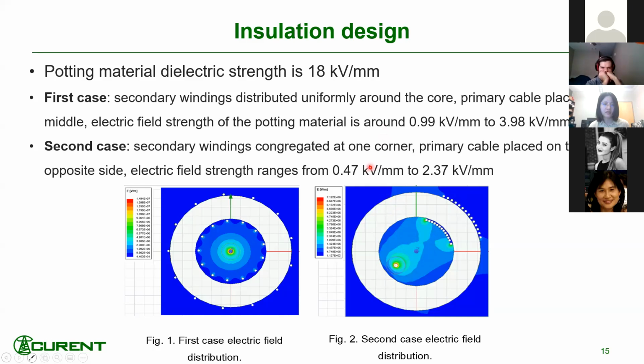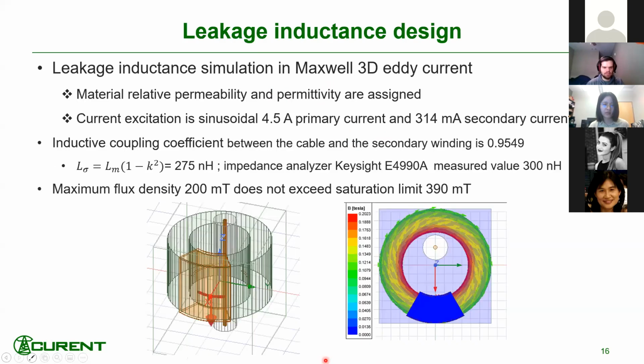So in both cases, the electric field strength is much below this breakdown voltage, which means this transformer would be able to sustain that high voltage. And another issue is the leakage inductance, because the cables and the windings are separated. So I try to simulate the leakage inductance to see how much this design would bring to the actual transformer.